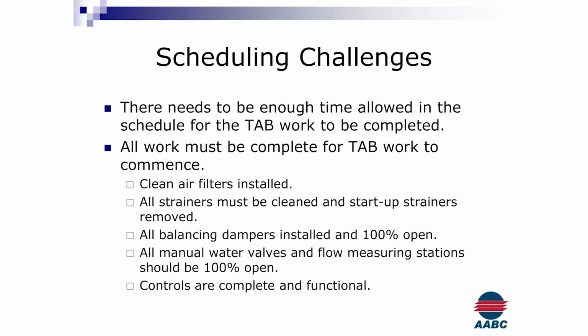There needs to be enough time allowed in the schedule for the tab work to actually be completed. And as I said before, whenever there's a delay, the deadline doesn't get extended. So what happens? The last kids off the bus, commissioners and tab firms, we all have to expedite our work, but they still want it done at a high level. So if we can coordinate at the beginning and really emphasize to the GC that you can't let these dates slip, because if you do, I can't deliver the product you want. That's really an upfront contract with the GC: these are hard dates, and to do my job correctly and per the spec, I need 16 weeks.